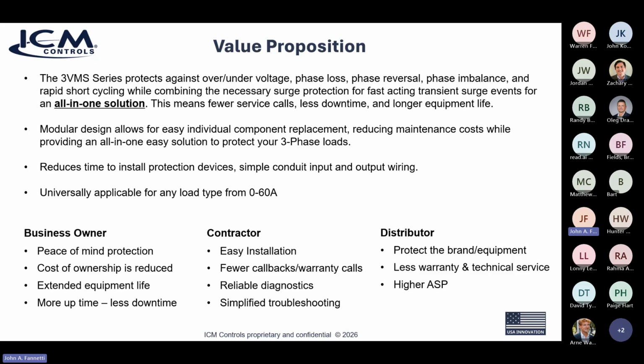Modular design for easy individual component replacement, reducing maintenance costs while providing you an all-in-one perfect solution for three-phase loads. Now, when you have a nice, quick modular design, it reduces the time to install. Also, it's simple conduit input and output wiring. So it's easy to install, reduces time. That means in and out, better for the customer, better for the contractor. Universally applicable for any load from 0 to 60A as well.